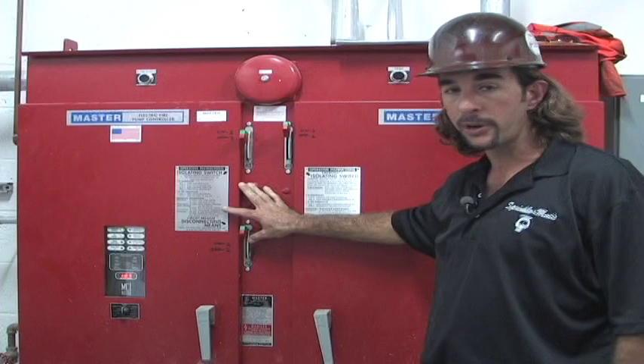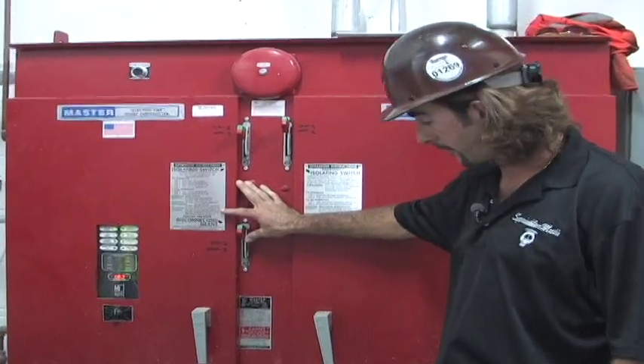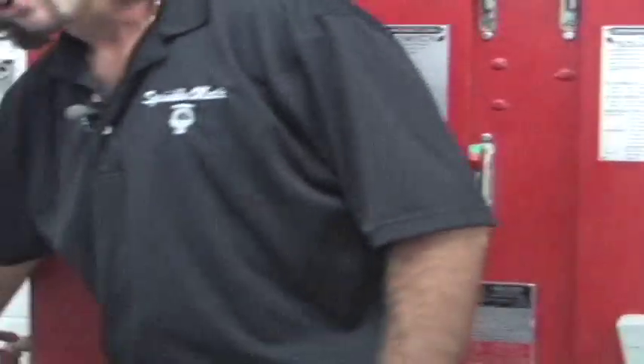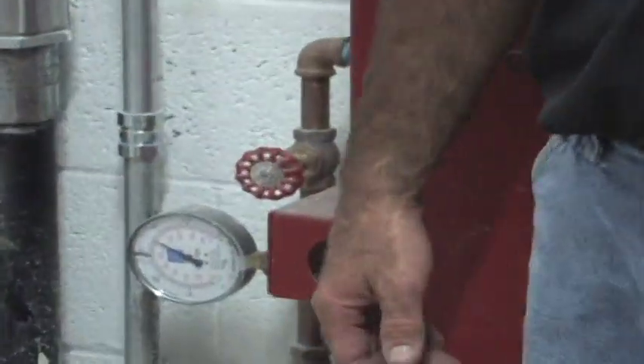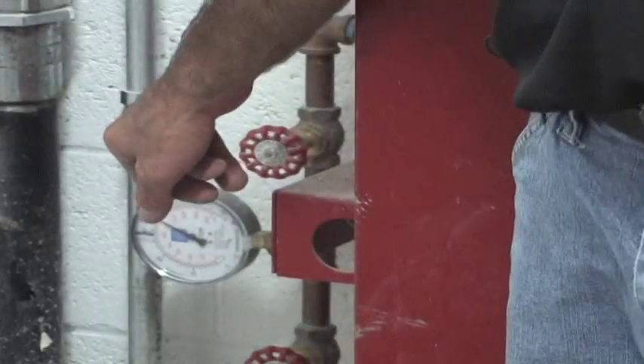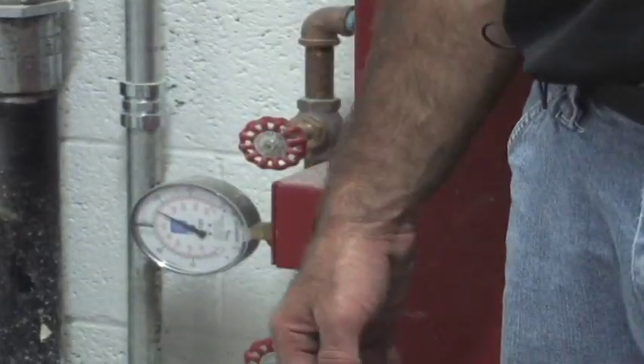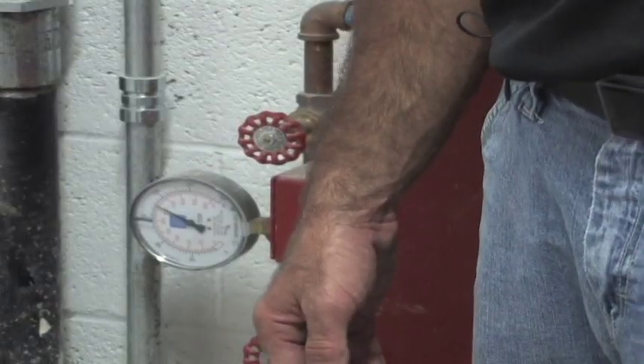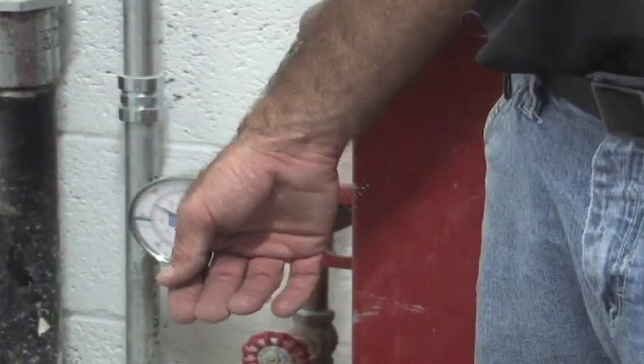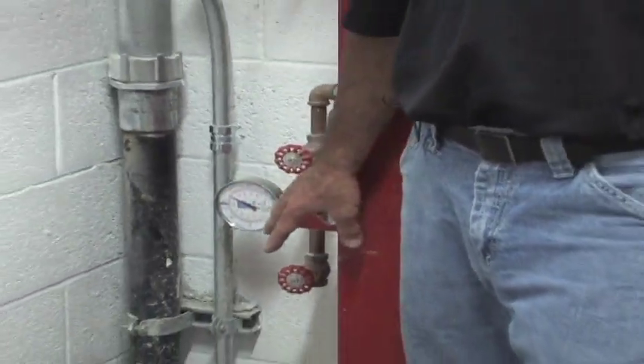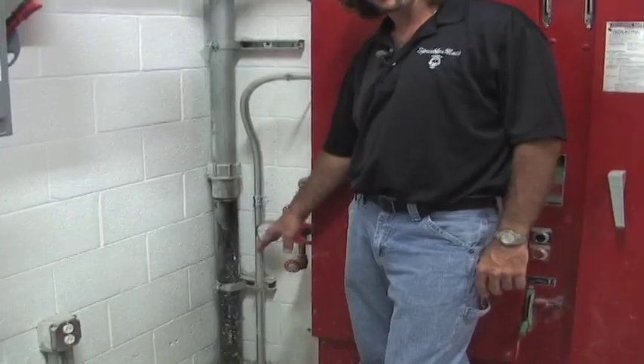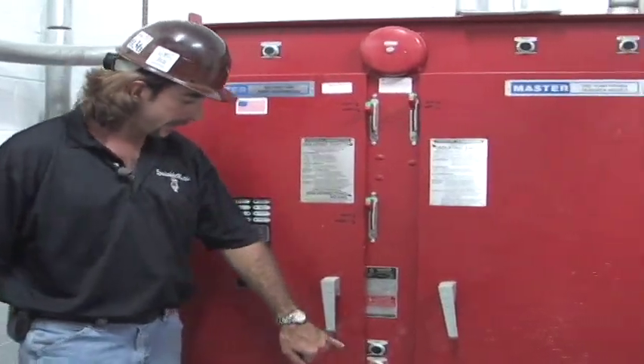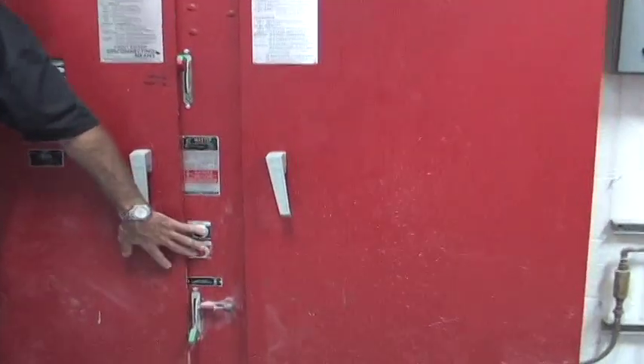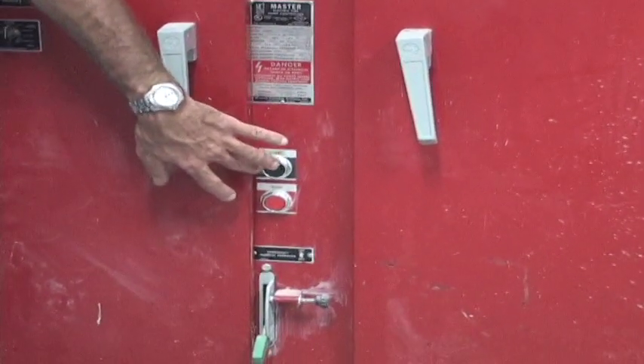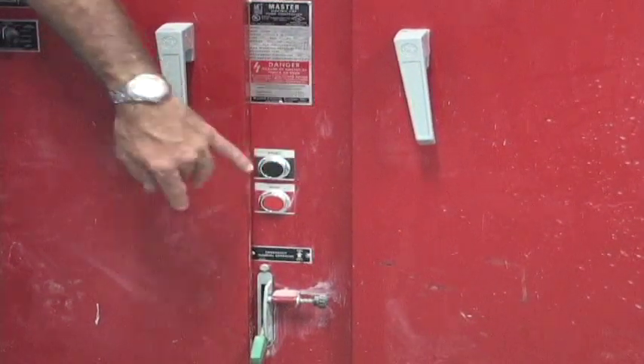As I said, the fire pump does work in an automatic and a manual position. We have our sensor line, which is our 1/2-inch brass feed that comes off the discharge side of our sprinkler system. Once that pressure gets below 150, which is 10 pounds lower than where the jockey pump should automatically start, our fire pump's going to start up. Again, if our fire pump starts up due to a loss of pressure, once it builds up its pressure, it will shut off in 10 minutes automatically. If for some reason somebody comes out here and hits the start button, we have to manually stop it. The fire pump does not have an automatic stop feature. Once it's pushed start, you'd have to push the stop button.